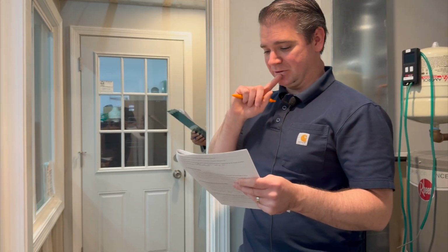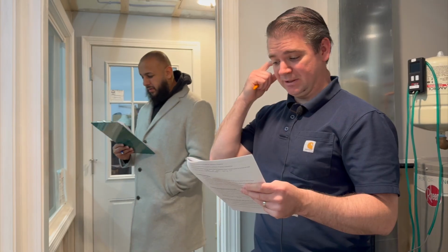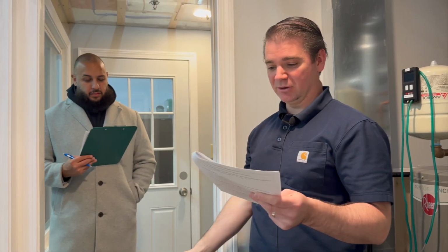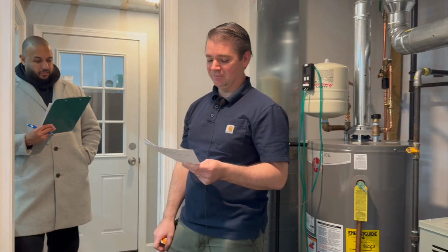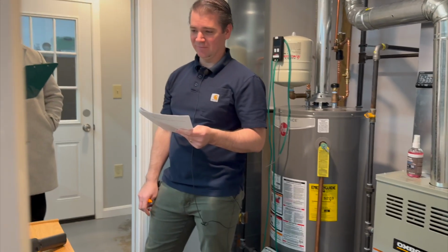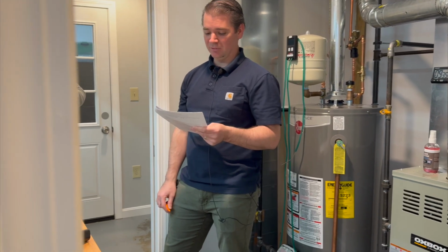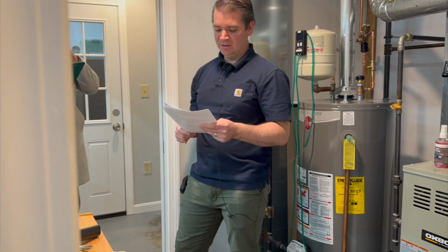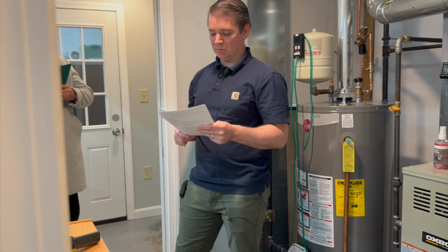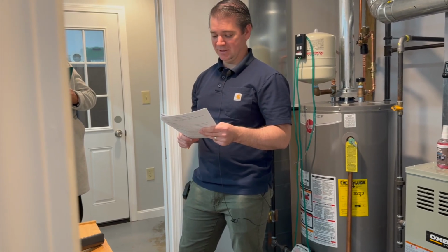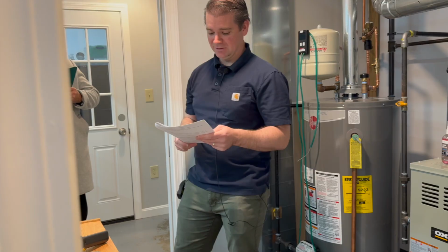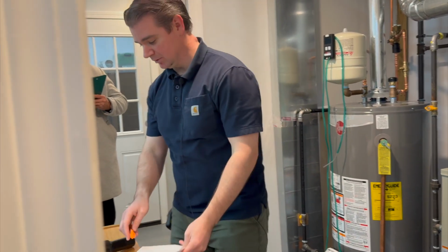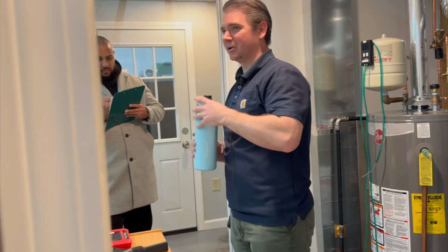Verify that solid fuel combustion appliances are in an appropriate setup for the blower door testing. If none, describe the appropriate conditions. I said that earlier. If there was a wood fireplace, obviously we can't have any warm ashes or an active fire. We have to delay the test. So if there's ashes in the fireplace, we want to either clean it out, or put a wet towel or newspaper over it, and make sure the flue is closed. Set up the house for blower door testing in accordance with one of the approved methods listed in ANSI BPI 1200. So at that point, it's just time to set up our blower door test and drink some water. Any questions so far?